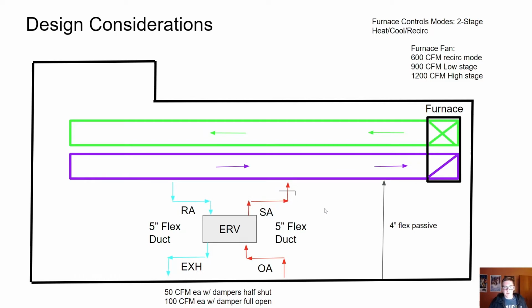So I'll talk about the importance of balancing, but one design criteria to keep in mind, you want to try and keep the runs on this side equal in length to the runs on this side. That makes balancing it easier, and you can keep the dampers roughly in the same positions. If you have vastly different lengths for your runs on the exhausting side versus the outdoor air side, you may run into a little more difficulty balancing it because those two dampers are going to have to be in unique positions.